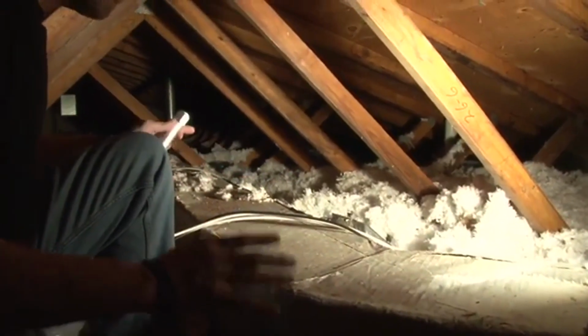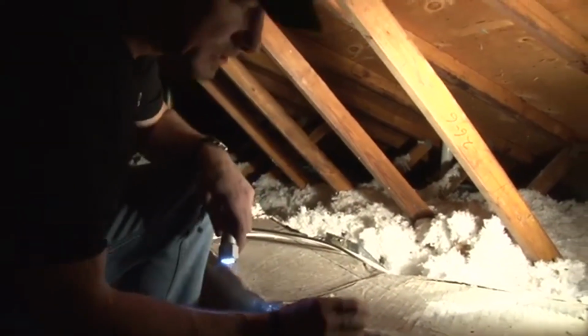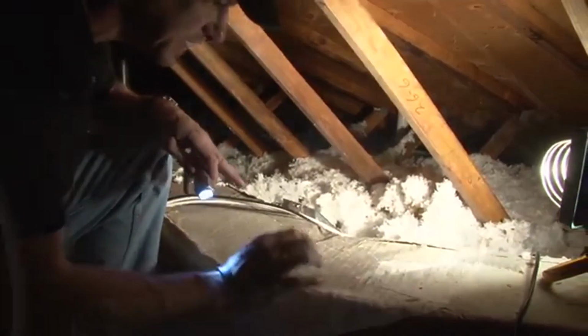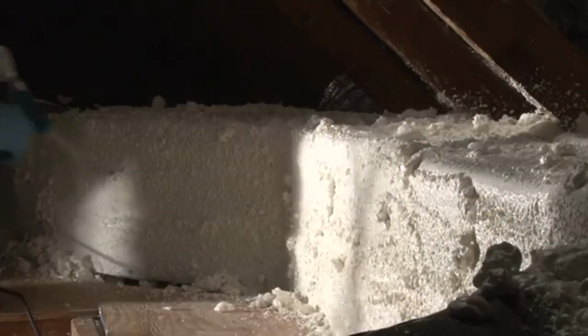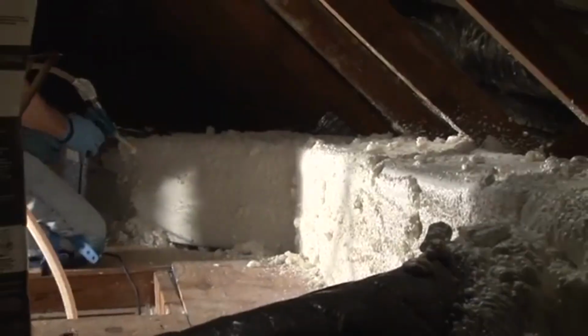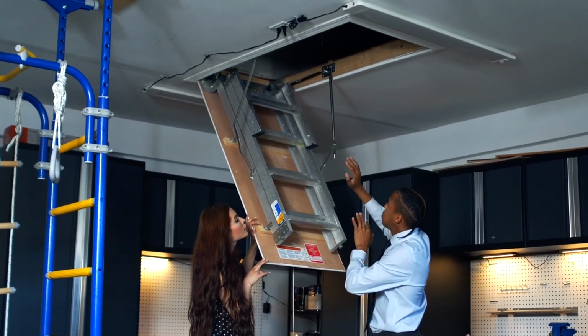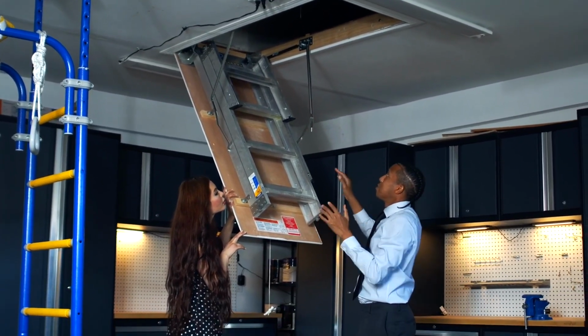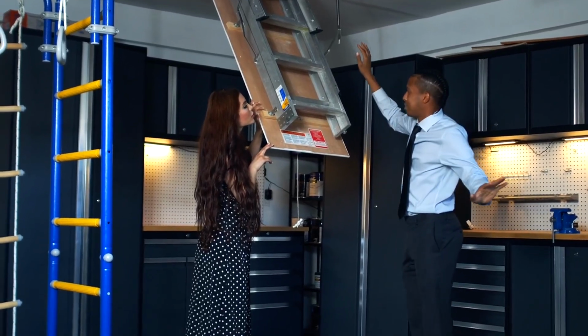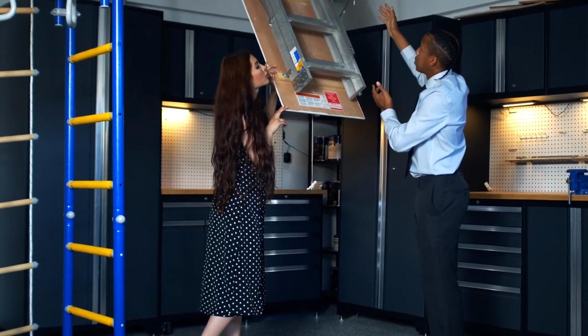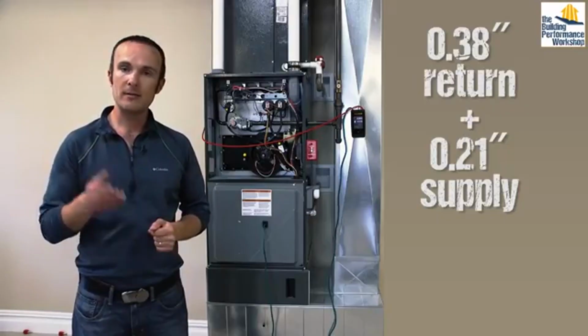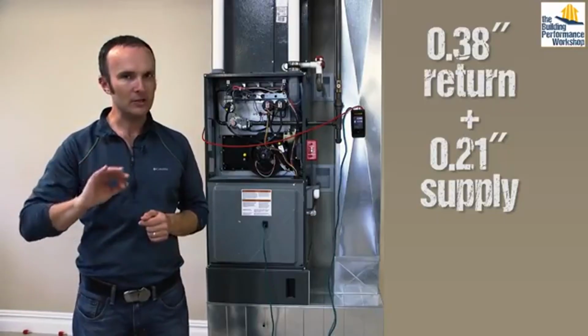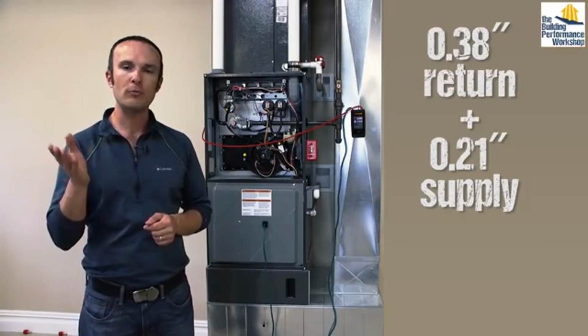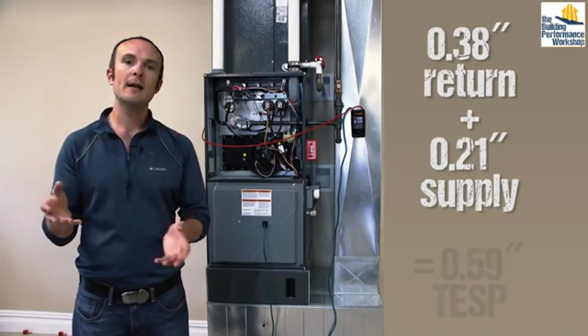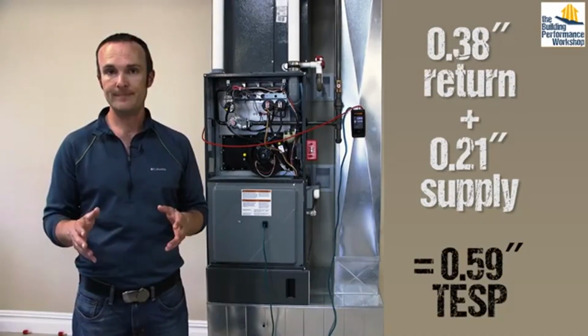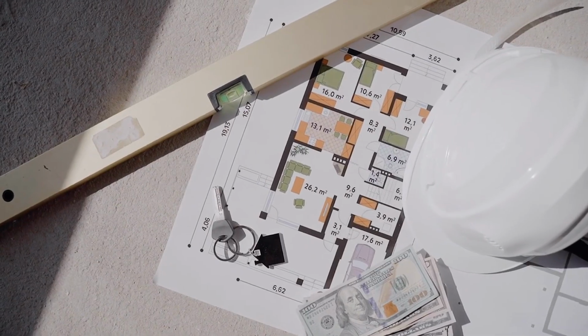And maybe they're right, but maybe they're not even looking at the right thing. Ductwork is the distribution system for your entire HVAC. If it's leaking, if it's undersized, if it was routed poorly when the house was built, it doesn't matter how efficient your new unit is. You are conditioning the air inside your walls and attic instead of inside your rooms. Studies from the Department of Energy have consistently shown that duct leakage in the average home results in somewhere between 20 and 30% of conditioned air being lost before it even reaches the living space.